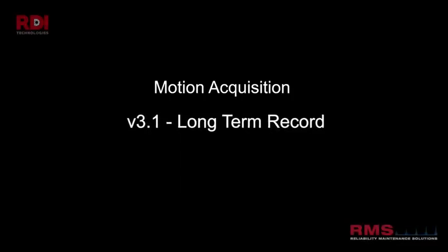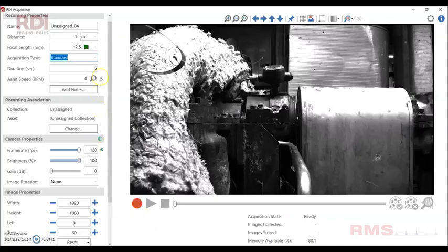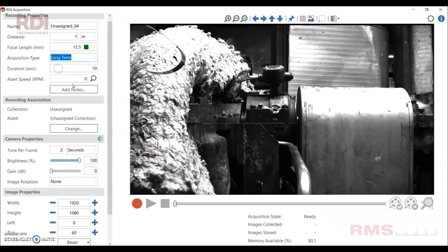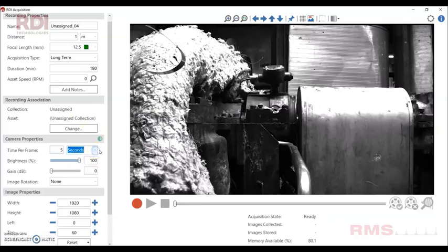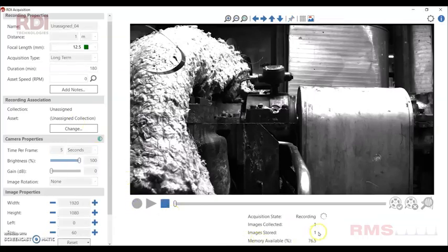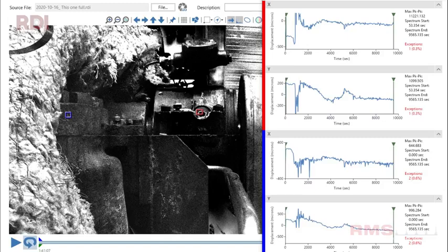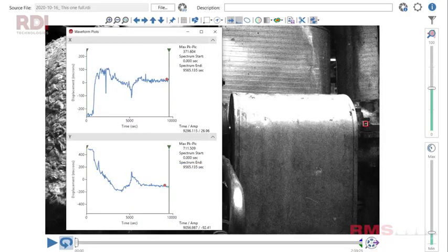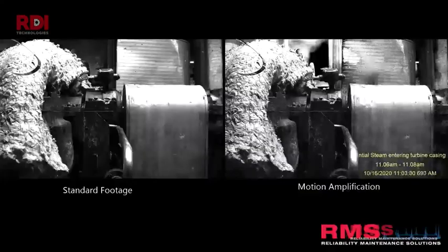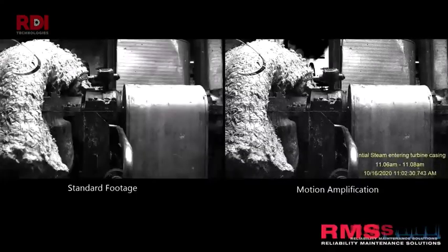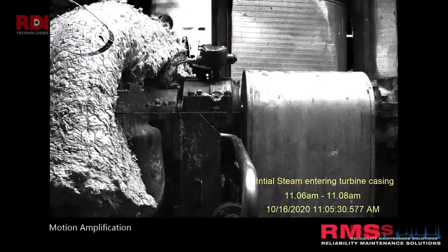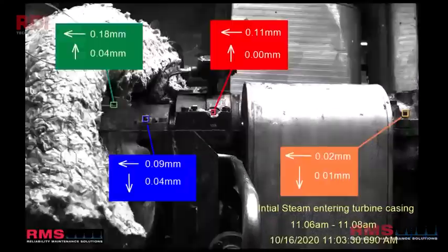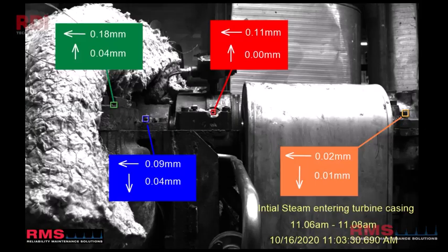Long term record. This is almost like a time lapse. So we can actually do stuff like thermal growth over many hours. We put a duration in. Here I'm going to put 180 minutes, but it could be as long as you want. And then how often do you want to capture an image? I've put five seconds here, but it could be minutes or hours. And then we set record. And then every five seconds in this case, it's going to take an image, which will build a video which we can then look at the data. And here was a turbine warming up. It was offline and we're doing some thermal growth measurements over a long period of time. I think it was two and a half hours. And then we can actually play the video. And the one on the right shows you the machine rocking backwards and forwards as it heated up. And there's the thermal growth measurements.